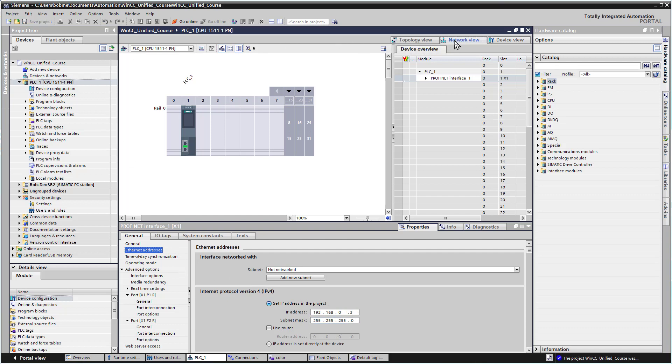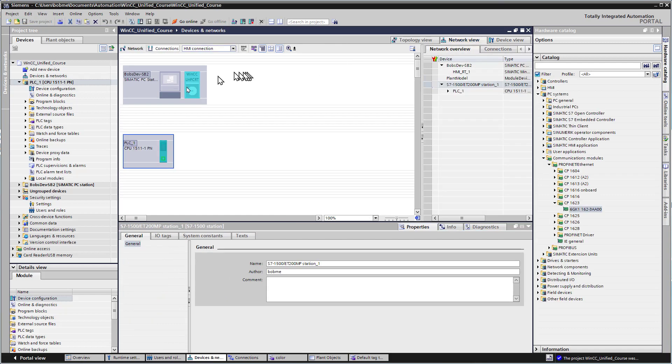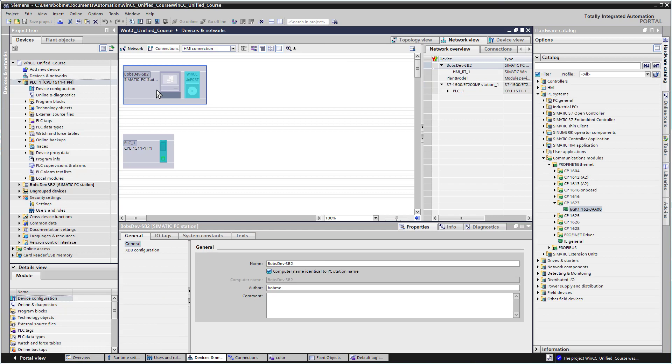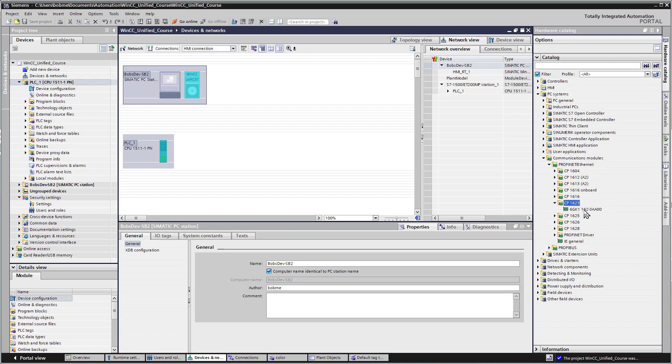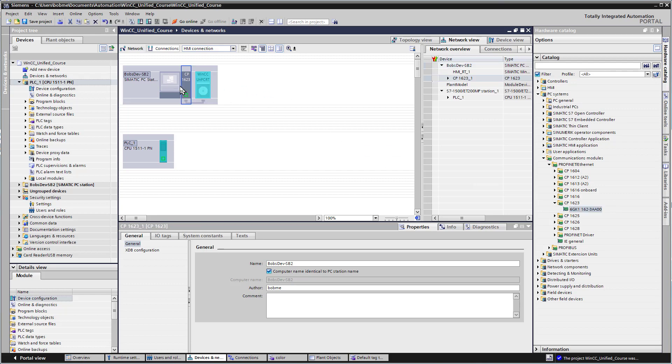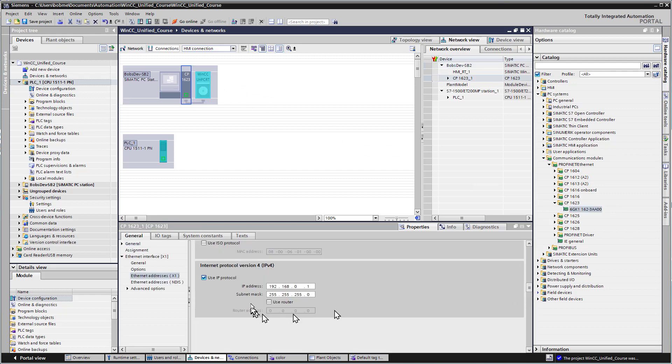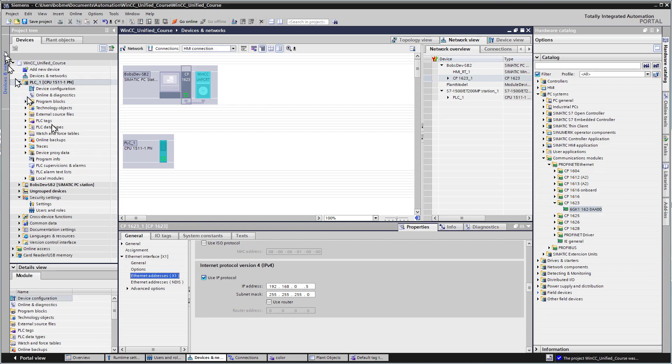Going back to our network view, I have to add a communication card to our runtime PC. Going over to our catalog under PC Systems, Communication Module, I'm going to add a CP 1623 and drag it up and drop it. It's going to default to 192.168, I'll make that .5 and save.